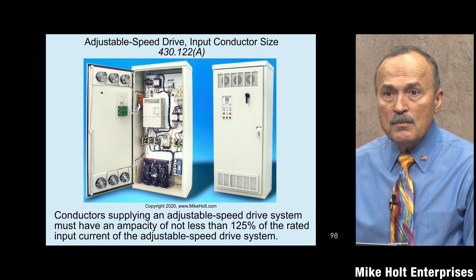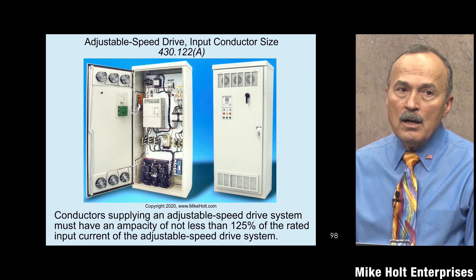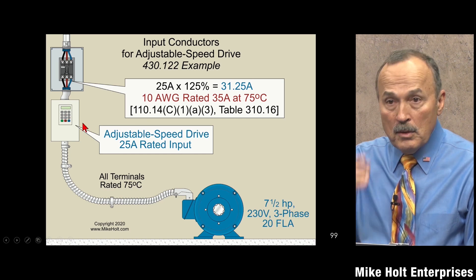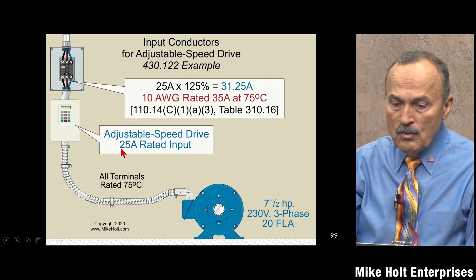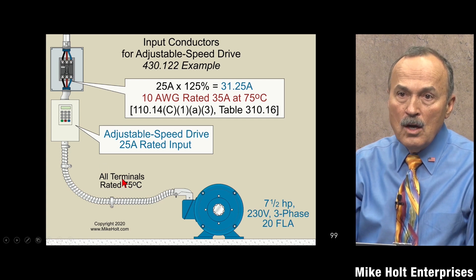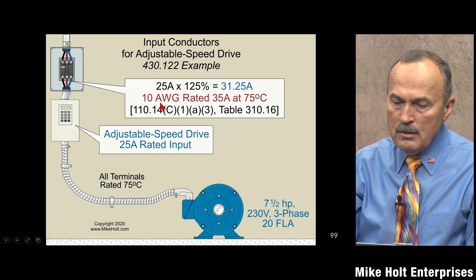Wires from the drive to the motor are branch circuit conductors to a motor, so those are sized at 125 percent of the motor FLC. For the conductors to the drive: if the drive nameplate and instructions say 25 amperes, multiply by 125 percent = 31.25 amperes. At 75°C, using Table 310.16, 10 AWG wire is rated 35 amperes — that would be the conductor size.